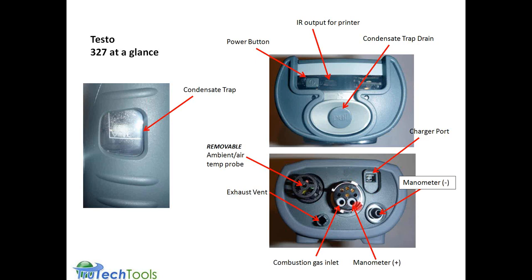The probe connection, this is the flue gas probe connection. You might be able to see the inscribed arrow with the flat point. You want to line up the arrow that's also molded into the metal probe on the male side of the connection. That's the point you want to line up in order to key it correctly. This port here with the manometer plus on it, that's the hose that connects to the draft sensor, and the manometer minus is over here. There is an adapter available for this to do gas testing, or you could just slip a tube securely over the complete opening at the tip of your probe if you wanted to run a pressure test with the plus side of the manometer.